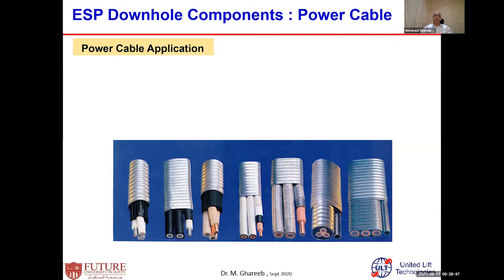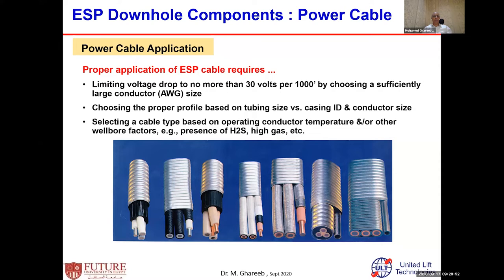Then, power cable applications again. For ESP power cables, when I select the power cable and apply it, I need to remember one point: how to select the power cable and where to apply it. One of the very important things for the power cables, while running in hole, is to keep in mind that when I choose the power cables, the voltage drop should be no more than 30 volts per 1,000 feet. That's what that means.